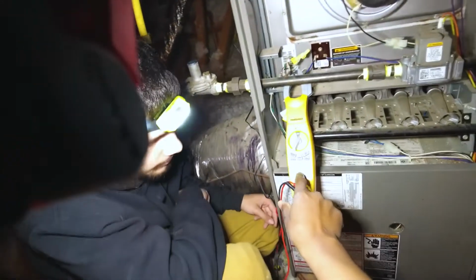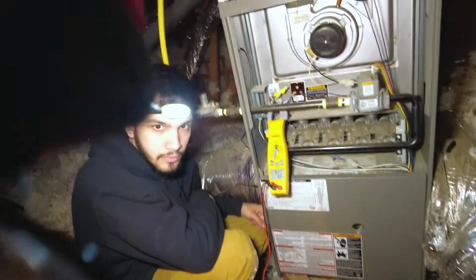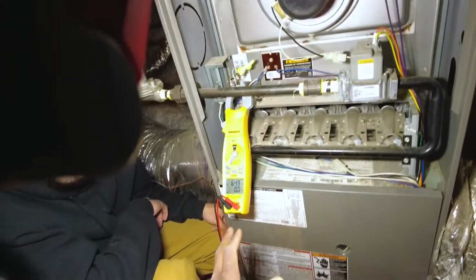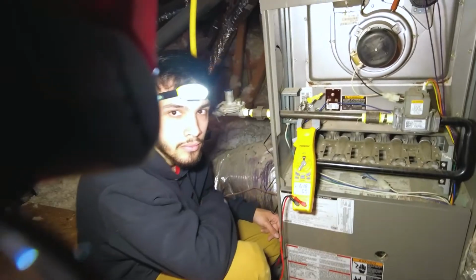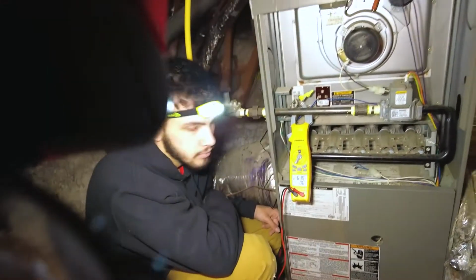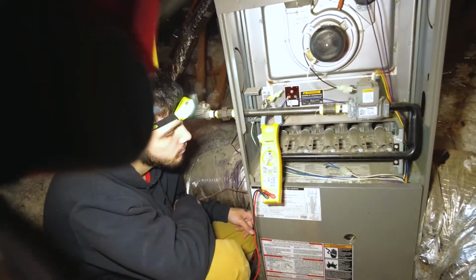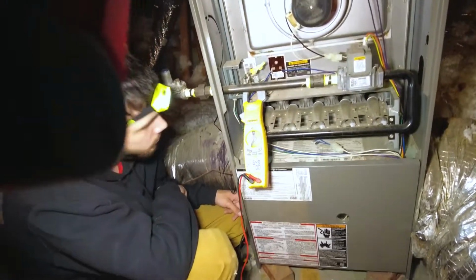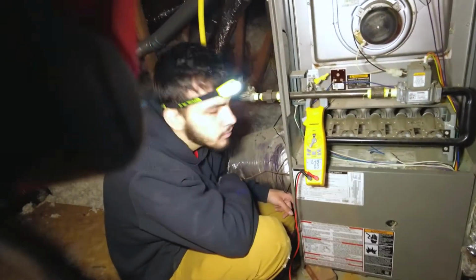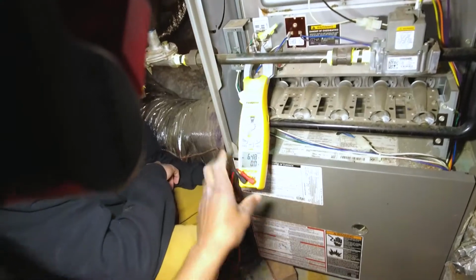So as you can see on our meter, showing 6.4 amps. But that's the blower, that's close enough, I'm not gonna lie about it, but you're usually gonna be about 0.3 amps high because the contactor and the board, the transformer essentially, everything on the low voltage side is pulling about 0.3 amps. So that's closer to 6.1 amps.